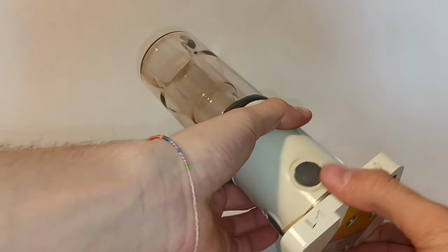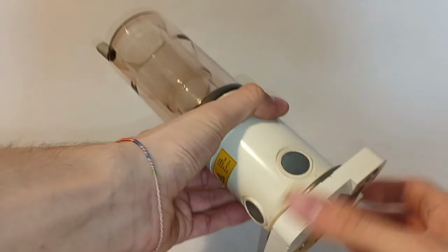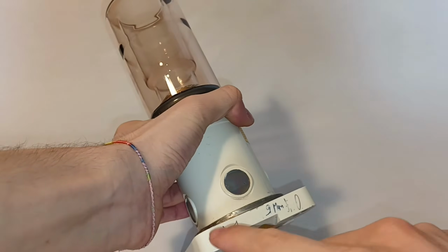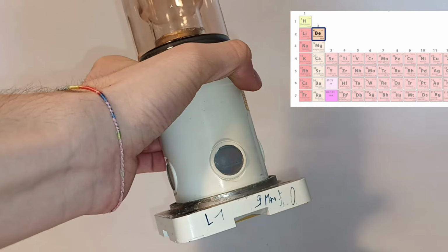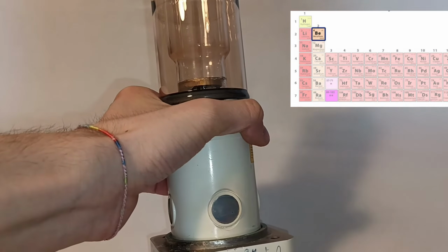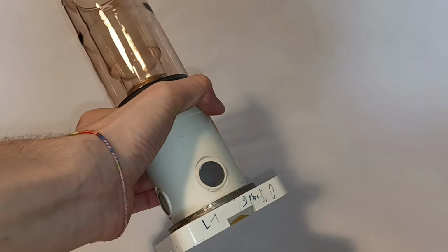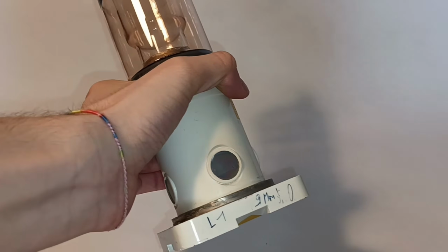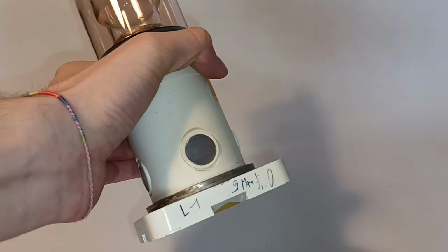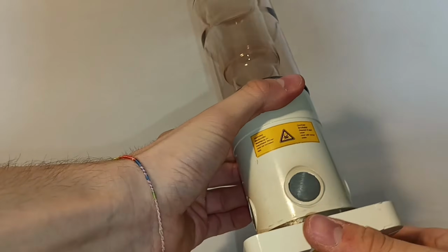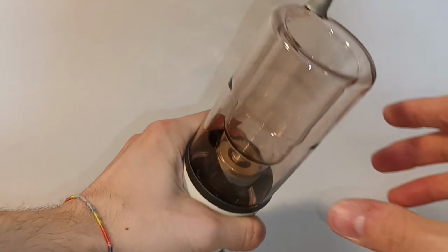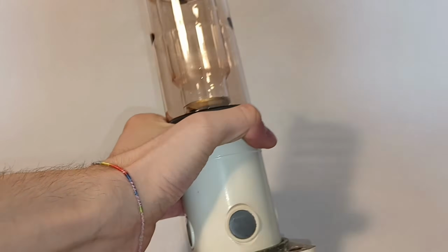In this case, the X-rays come out of these 4 windows down here at the base of the tube. They are made of beryllium, a metal that has a really low atomic number. In fact, it is at the right of lithium on the periodic table, and this makes it a really great choice for letting through X-rays, because it doesn't absorb them, having a low absorption coefficient. In the tube I showed you earlier, the anode was the part made of tungsten.